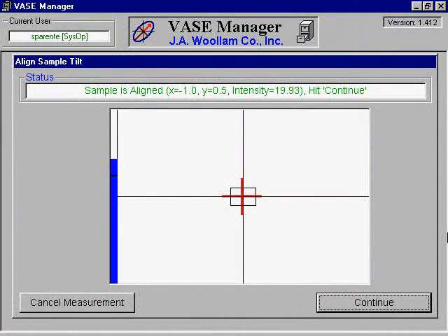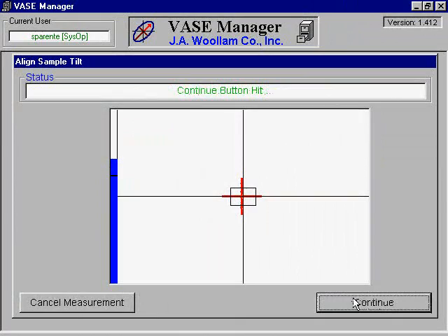You should never be too forceful with the alignment knobs because this could damage them. Once the crosshair is centered appropriately, you should be able to see a blue bar on the left side of the screen. The intensity will need to be above the minimum line for the scan to take place. When everything is set correctly, click Continue.